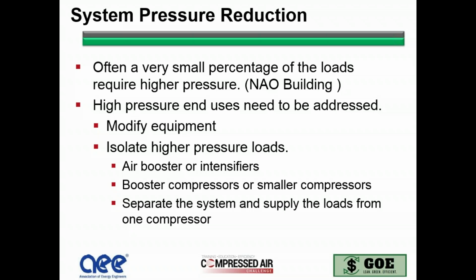Often, there's a very small percentage of loads that require higher pressure. One of the ones that I ran into as the energy manager at Ford, we were doing audits, and in the most unusual spot, I was doing one of an office building. We had a North American automotive operations building. It was a 14-story office building, and I was doing an energy audit of it, and of course expecting to find things like lighting and HVAC, etc. Then I found a compressor that they had running at 90 PSI. It was an on-off compressor that was running to maintain anywhere from 85 to over 100 PSI.